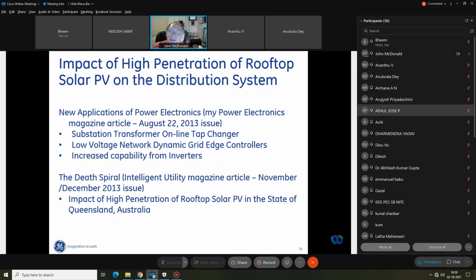The reason I wrote this article for Power Electronics magazine is that we need new applications of power electronics for the grid. One example is the online tap changer. As we implement more renewable, distributed generation and the penetration increases, it's no longer feasible to use mechanical controllers. Their lifetime is too short because the grid will be much more volatile with voltage and reactive power.